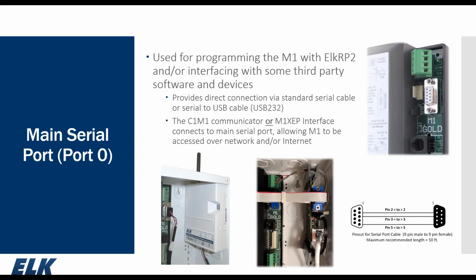Right below the telco connection is the RS-232 serial port that's built onto the M1. We call it port 0. It actually has 3 purposes, but can only do one thing at any given time. You can use this to direct connect with your PC for programming using the RP2 software. So using either a USB to serial adapter or a standard serial cable from your computer to the M1, you can plug directly in for programming.